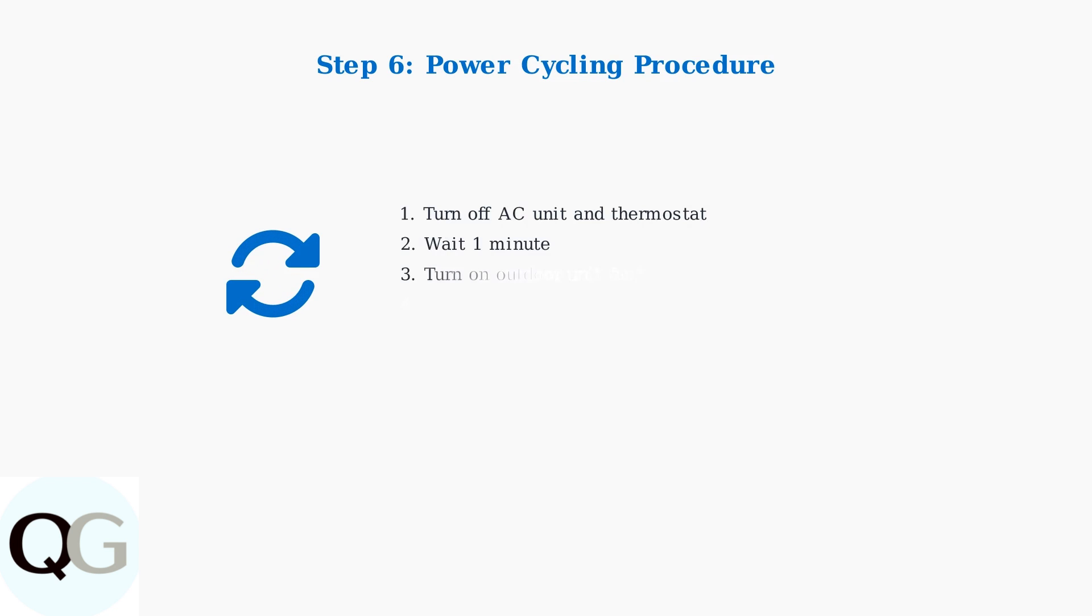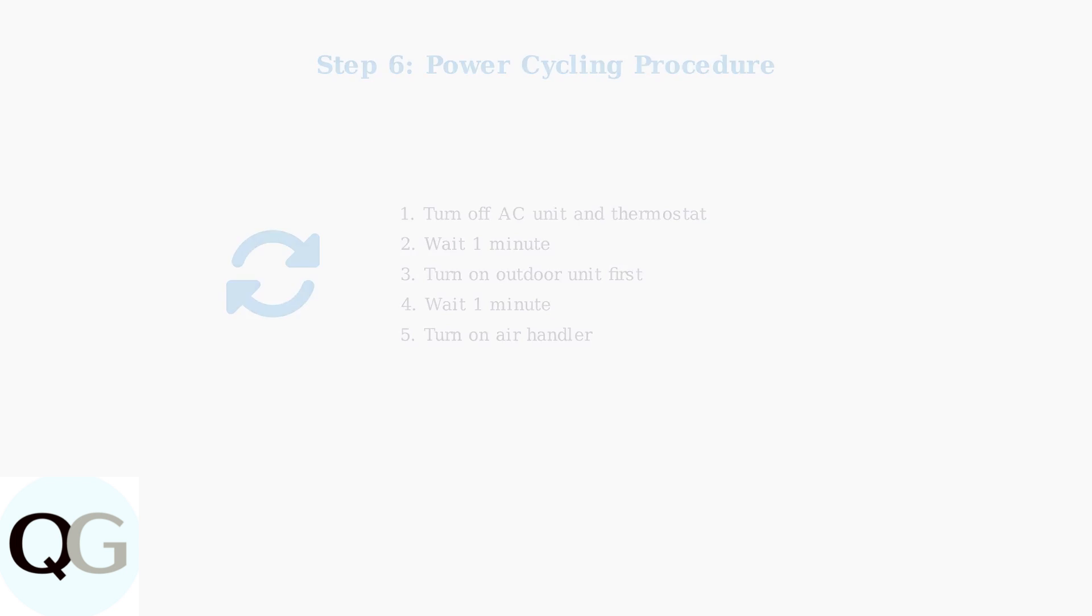Try power cycling the entire system. Turn off both the AC unit and thermostat, wait one minute, then turn on the outdoor unit first, wait another minute, and finally turn on the air handler.